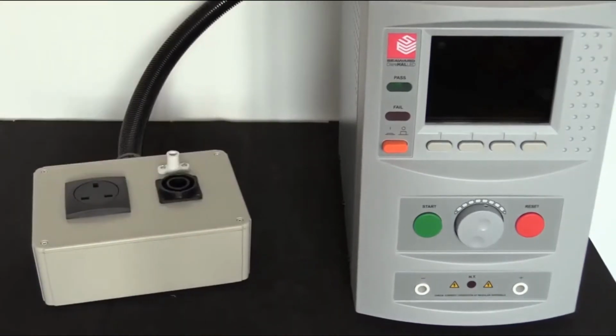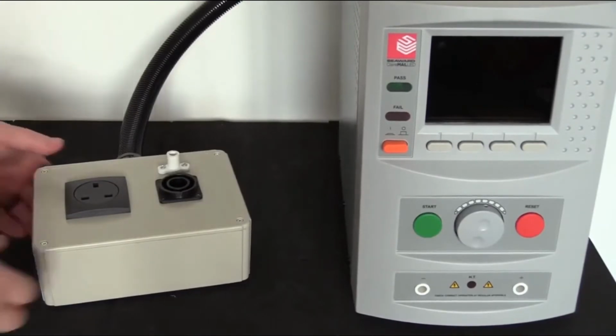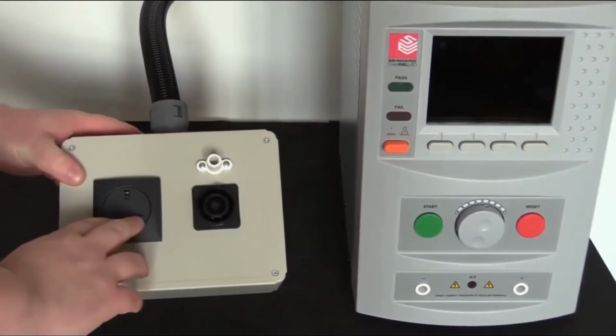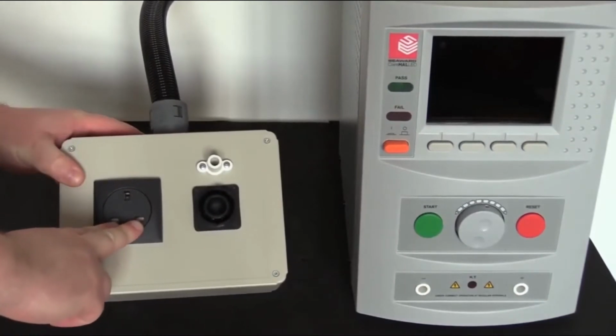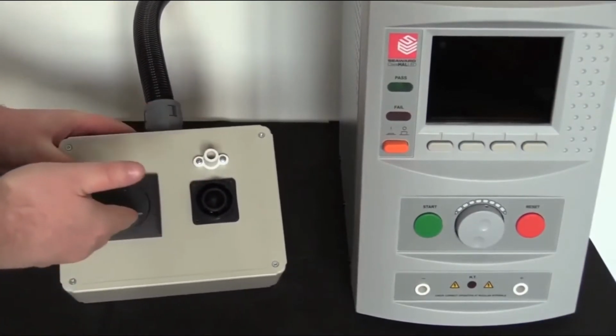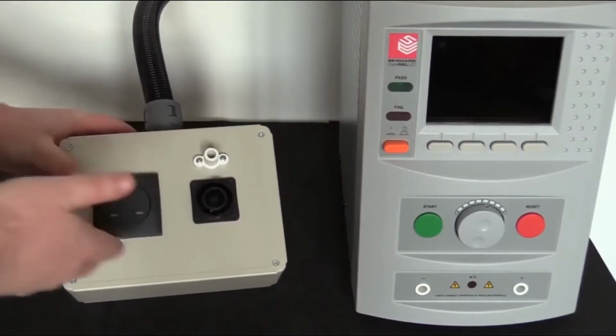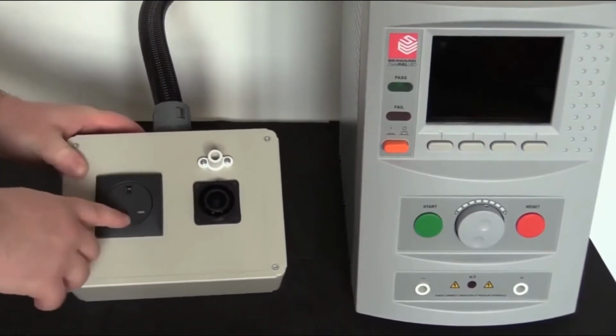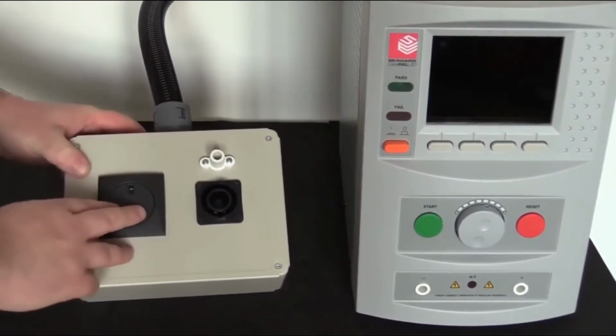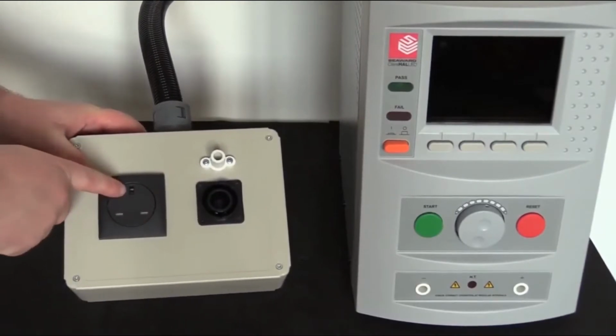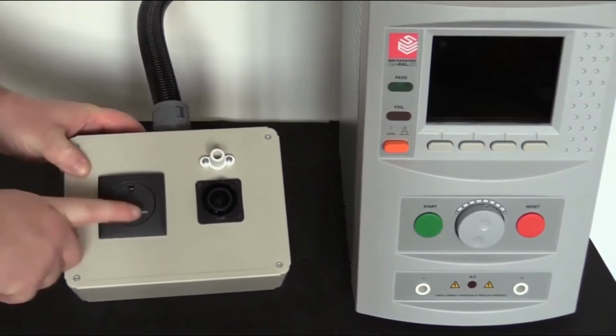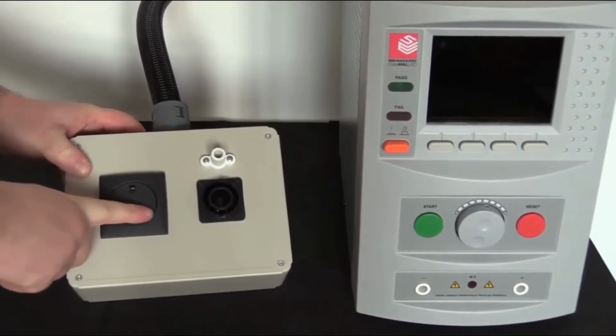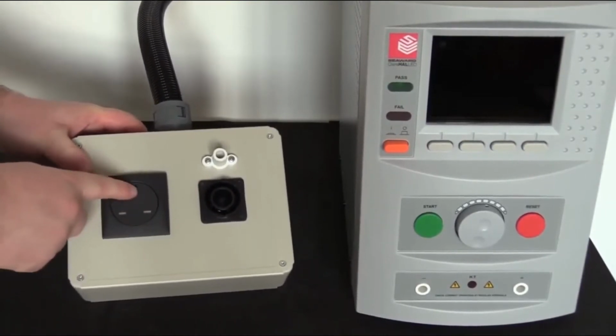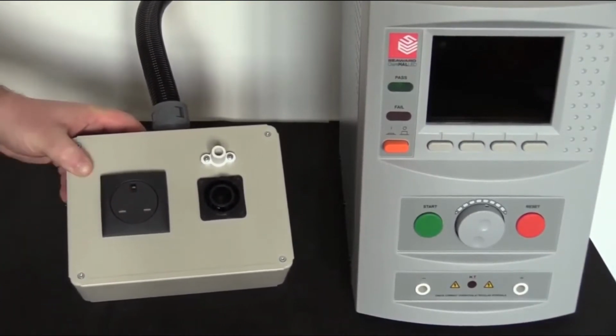Hipot testing can be performed in one of two ways. If we have a class 1 appliance, then Hipot testing can simply be performed between the live and neutral conductors strapped together. The HAL will strap these two together. There's no requirement for the operator to make any kind of connections. This is done automatically within the tester. So we would send our high voltage out through the live and neutral and measure any return into the instrument via the earth socket.